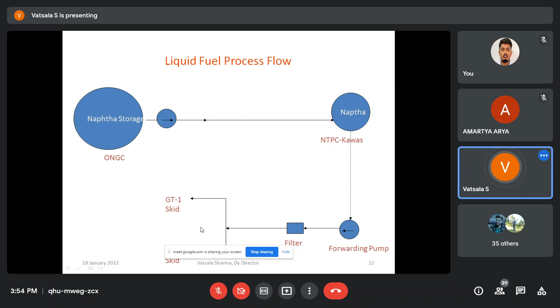And for liquid fuel firing in the gas turbine, as I have given you, liquid naphtha and HSD, and some more liquid fuels which are available, can be used in the gas turbine power plants. We can have the line GT1 like this. And if we have 4 GTs, 4 lines we have provided individually. Stop valve we have, this is the control valve we have, and here also we have the control valve. So the percentage opening of this control valve shows how much requirement we have in the power plants. Any more questions?